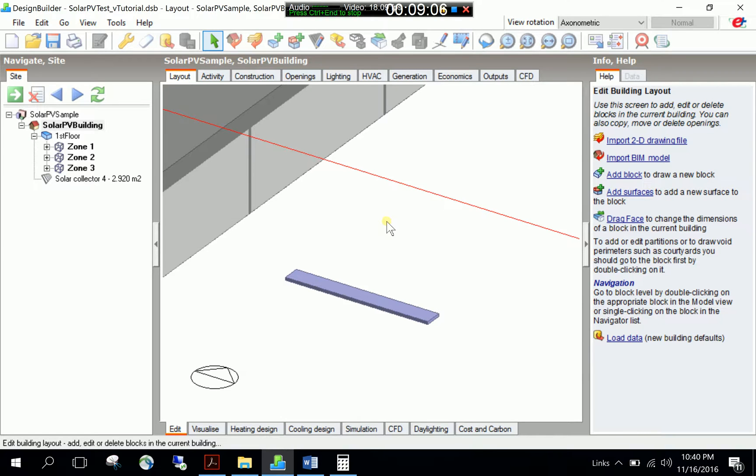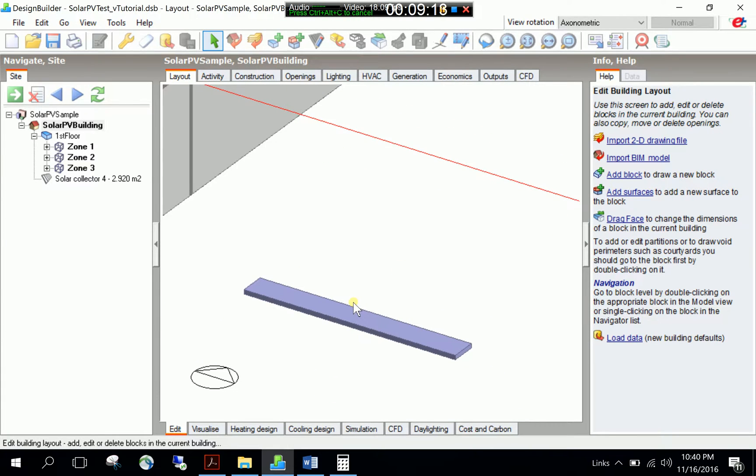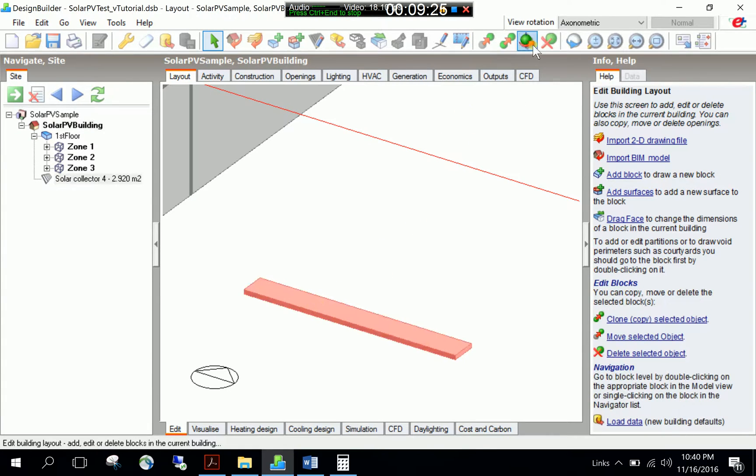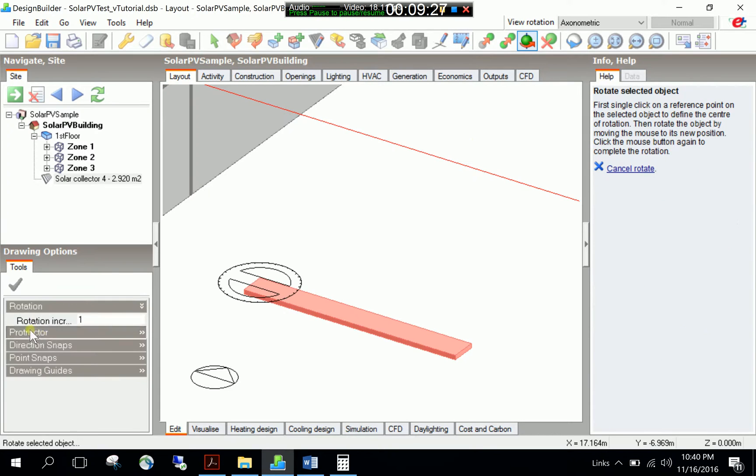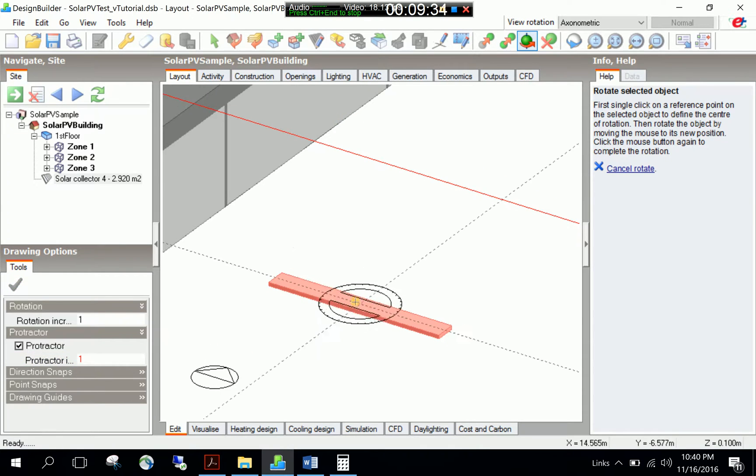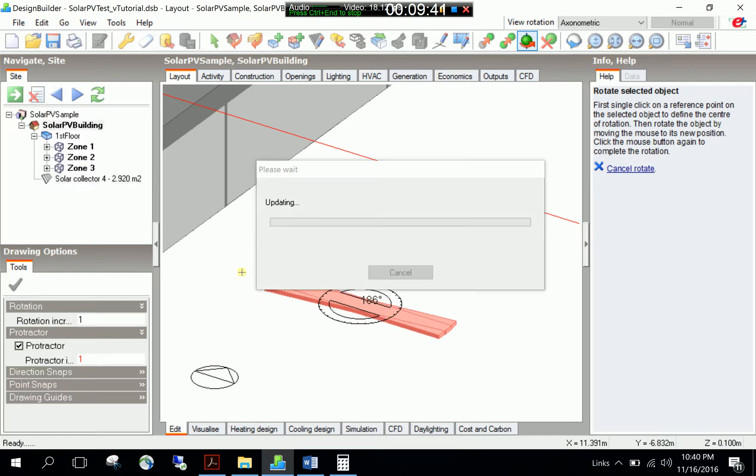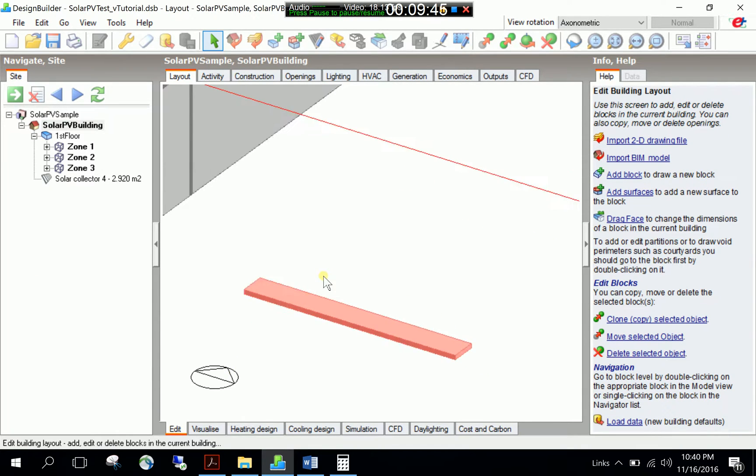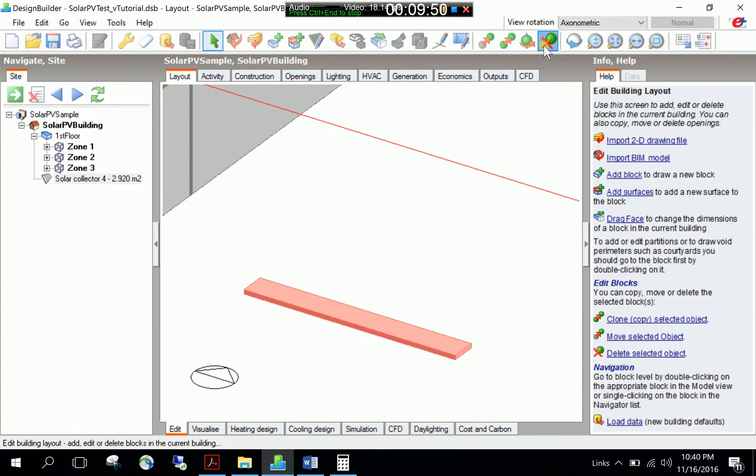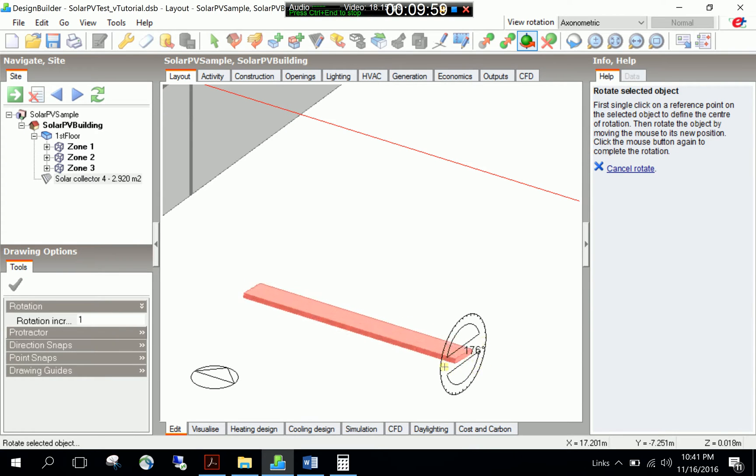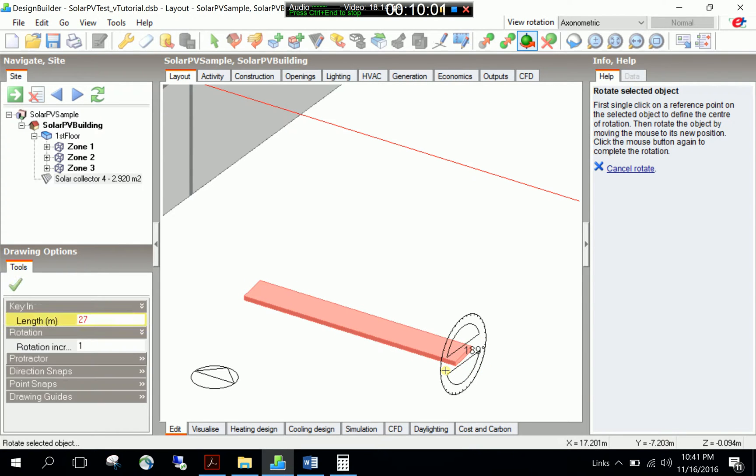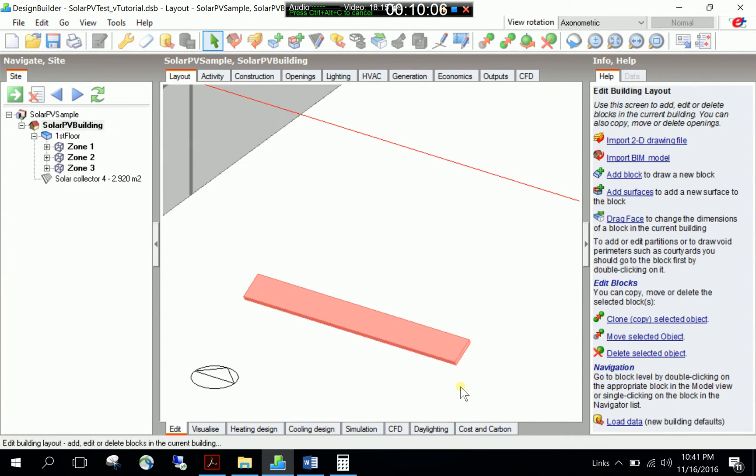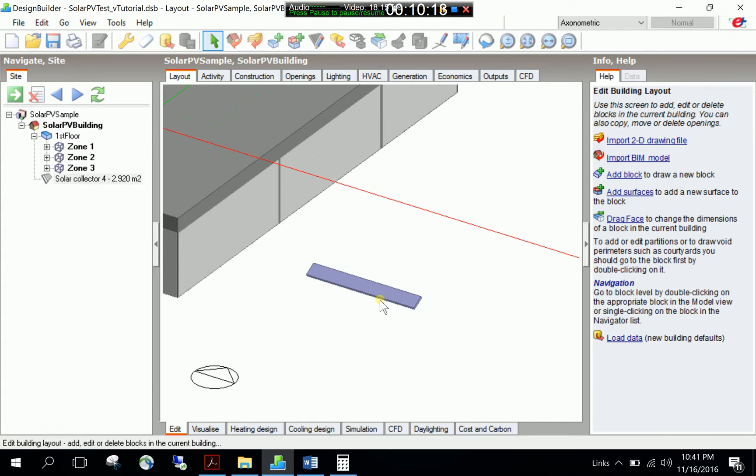And you can pay attention to changing the azimuth angle, which is the orientation or the horizontal angle of this PV array, which orientation is facing. Or you can work on the tilt angle, which is the vertical rotation angle of different solar PV arrays that you generated. So if you choose it and then say rotate selected, and I will create protractor, I will hit one degree increments. So this tool will help me. So I will select and I can rotate. I can change the azimuth angle, whichever I like in 360. But I'm not going to do that. I will assume the same south facing orientation for this array, but also I can choose it. And I again, I choose rotation and then just go to the side, pick the vertical. And now I can rotate in the vertical plane. I can give it an angle, say 27. And this PV array is tilted 27 degrees to the south. So this is usually tilted this way, the rooftop solar collectors.